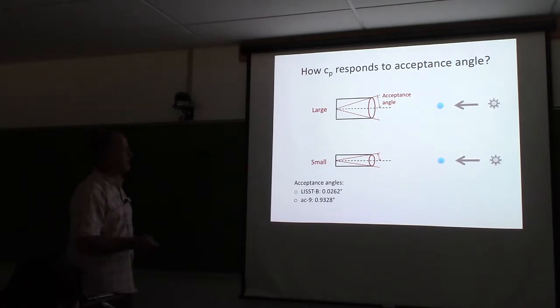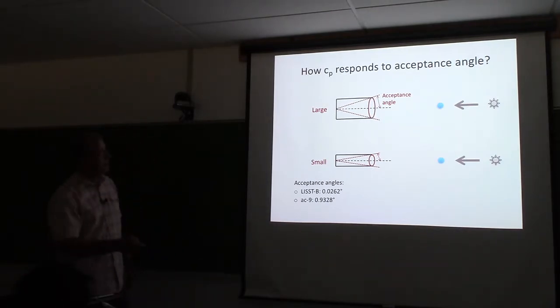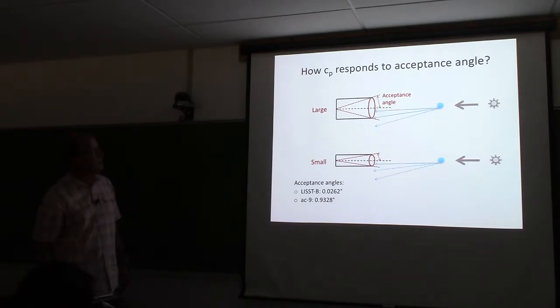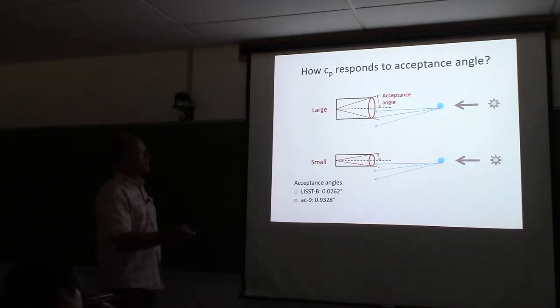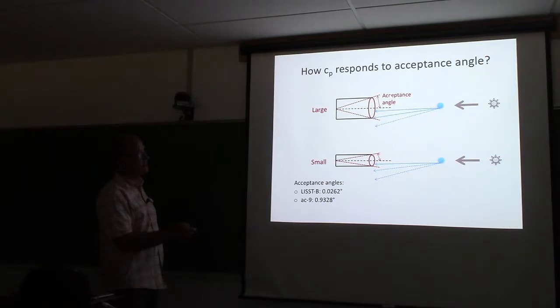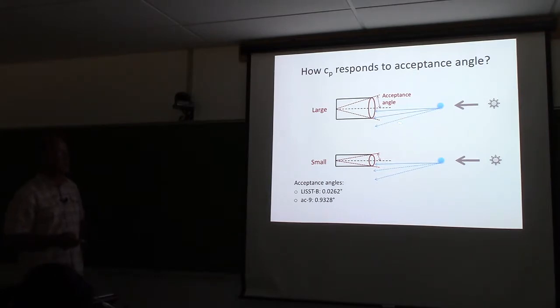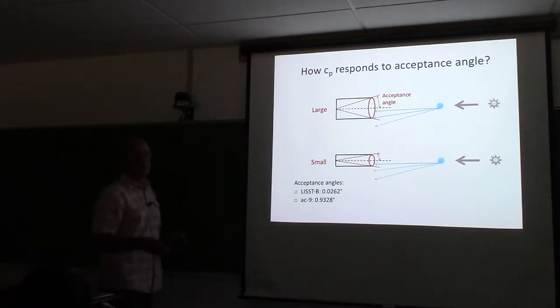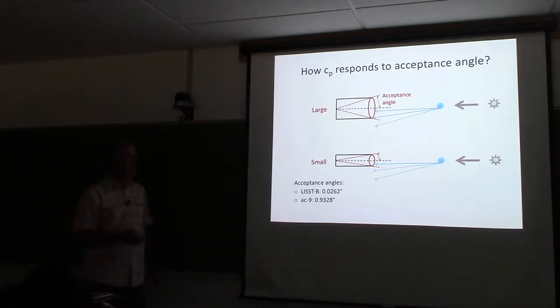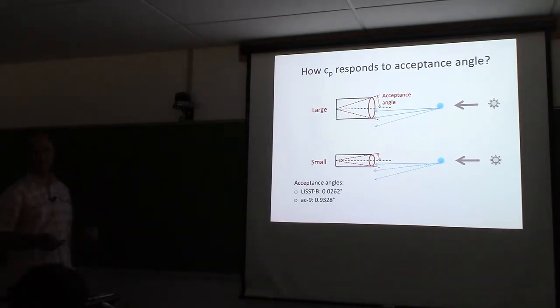Let's imagine we have transmitted light hitting a particle. We have a sensor with a large acceptance angle and a sensor with a small acceptance angle. With a large acceptance angle instrument, some of the scattered light will be interpreted as transmitted light - that's what the name 'acceptance' comes from. Light scattered at a larger angle won't be accepted as transmitted. With a small acceptance angle instrument, pretty much any scattering means the light won't be accepted as transmitted.